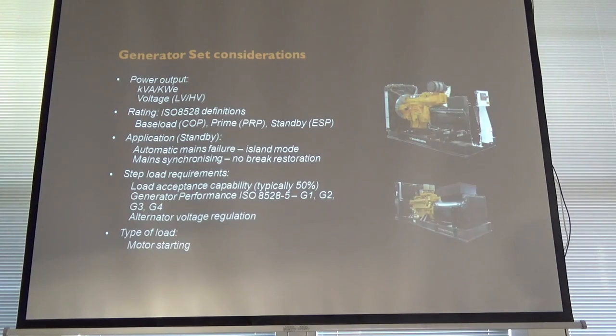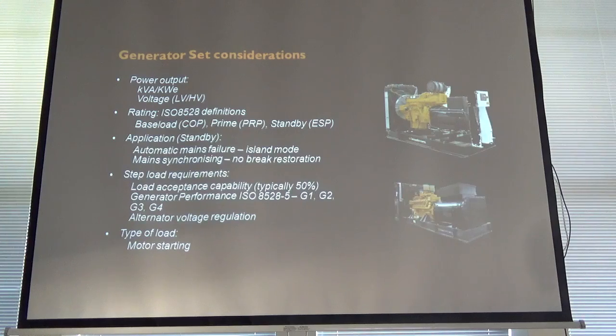There are various options. There's dead bus paralleling, or there are various starting scenarios you can have to get the sets to either excite together, or actually first one closes and the others very quickly synchronise and parallel with that first lead unit. There's quite a few ways of skinning the cat, but either way, 15 seconds is quite impressive, really.